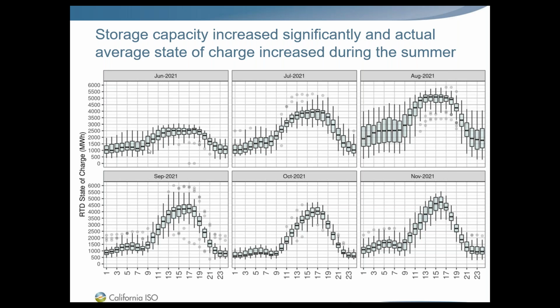So you can imagine these numbers will be even greater for average charge across the day in 2022. When we had just a few resources on the system, we saw them providing ancillary services, primarily regulation, for the California markets. As we got more lithium ion storage capacity online, those regulation markets became saturated, and more storage resources shifted to providing energy arbitrage - charging in the middle of the day and discharging in the evening during peak net loads and highest prices. That's the typical pattern we see for storage resources and anticipate for additional capacity coming online. Let's go to the next slide, please.